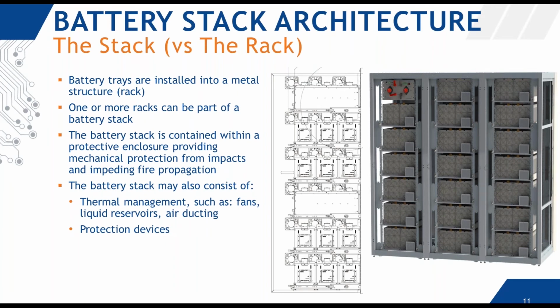And so we got these trays now. So trays are installed in a rack. That's kind of like the next level up. And multiple racks can be part of a stack. So if we were to connect all of these modules that are inside a single rack in series, and then place a few more racks beside it and wire those in series, and that's all managed by a stack switchgear, that's considered a stack. In UL 1973, this is what they refer to as a battery stack.